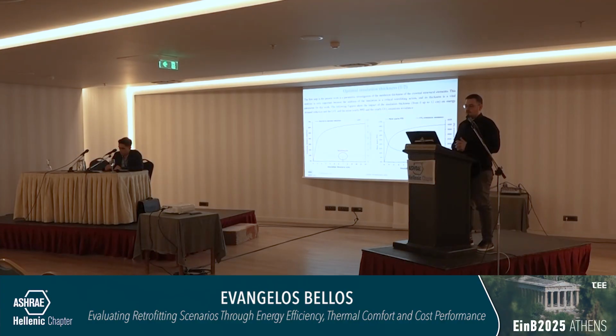As we can see, higher insulation leads to lower electrical demand and higher energy savings, which is a reasonable result. But the very interesting one is in terms of life cycle cost: there is an optimum insulation thickness, which is around 7 centimeters. Therefore, this value was selected as the optimum one for this retrofitting action.